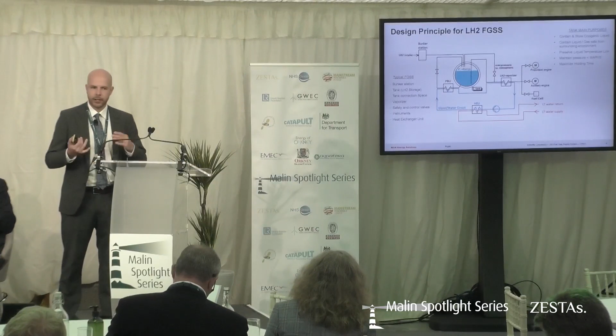So we store it in liquid form at minus 253 degrees inside the tank at 4 bar gauge. This overpressure is the driving force behind the process. So we press the liquid through the vaporizer. It's at 4 bar gauge. We just have a phase transition from liquid form to gaseous form. So we heat the liquid up from minus 253 degrees all the way up to plus 20 degrees, so we can distribute it in gaseous form to the consumer, which could be a fuel cell or a combustion engine.